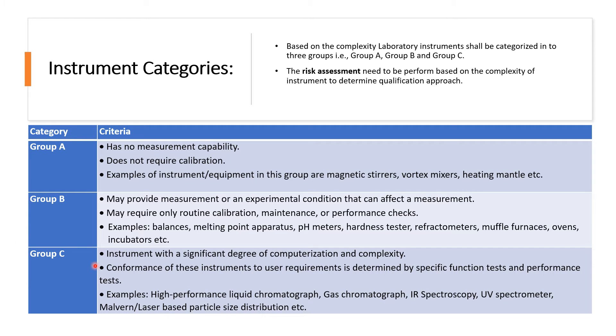Now Group C. Group C instruments have a significant degree of computerization and complexity. These are equipment connected with some kind of software and have a computerized system component. The conformance of these instruments to user requirements is determined by specific function tests and performance tests. Examples of Group C instruments include high performance liquid chromatography, gas chromatography, IR spectroscopy, UV spectrophotometer, and Malvern or laser-based particle size distribution instruments.